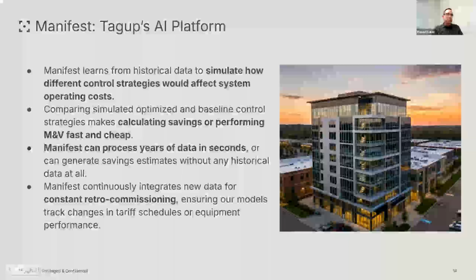That's what we call constant retro-commissioning, to take the latest data into account. We receive data for most systems on a 15-minute basis, and at least every hour we run that processing and recommend new control decisions.